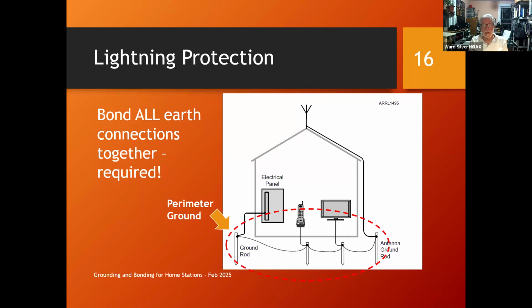Typically it's buried, so it's in contact with the dirt, but you want the minimum amount of voltage between these different ground terminals. You want your AC safety, your phone, your data, all that stuff, all going up and down together. They won't be at 0 volts, but you don't want really high voltage between your different systems. And that voltage difference is what causes a lot of damage. You hear these stories all the time. Thunderstorm rolled through. I left the shack. I was in there watching TV, and all of a sudden I saw the flash and this big green arc jump from my computer to my entertainment system. And now nothing in the house works.